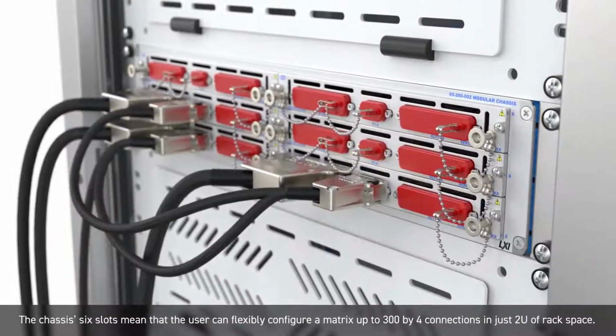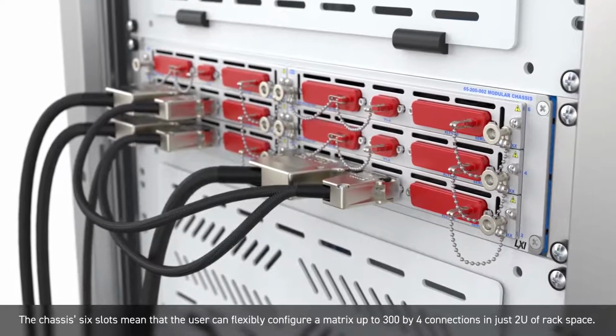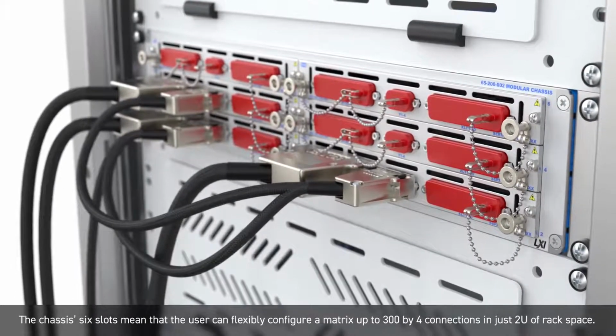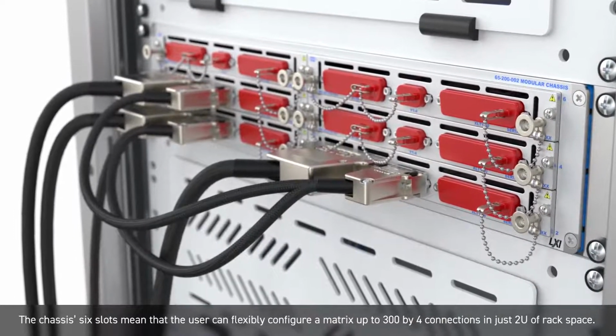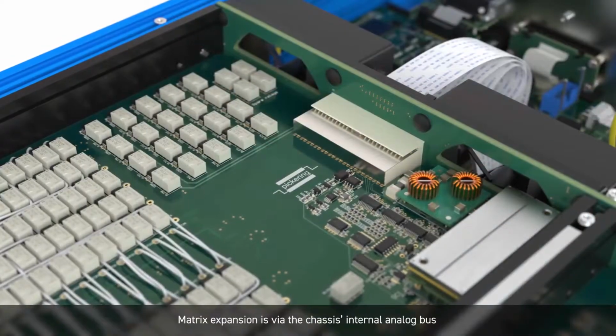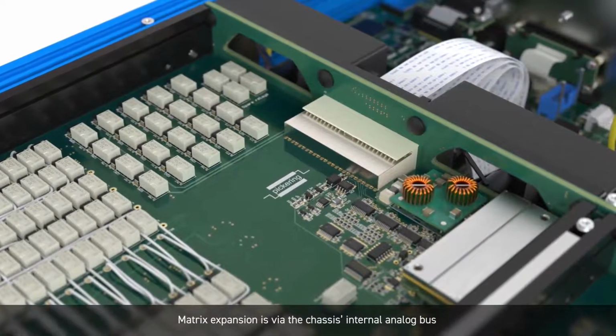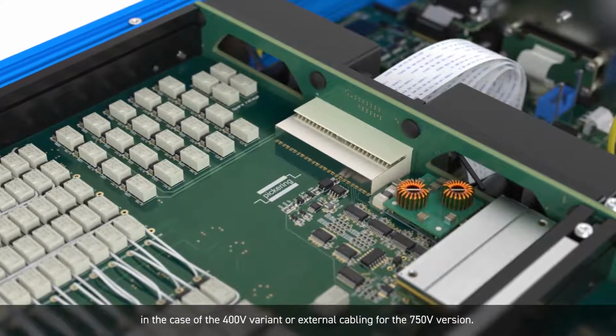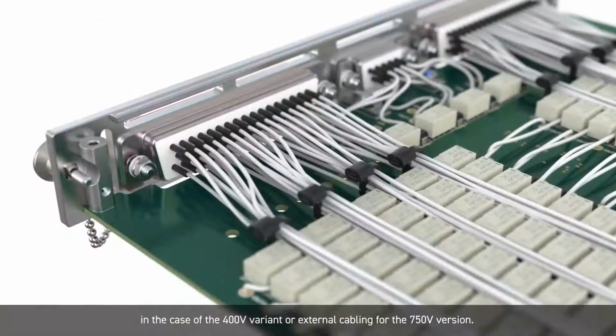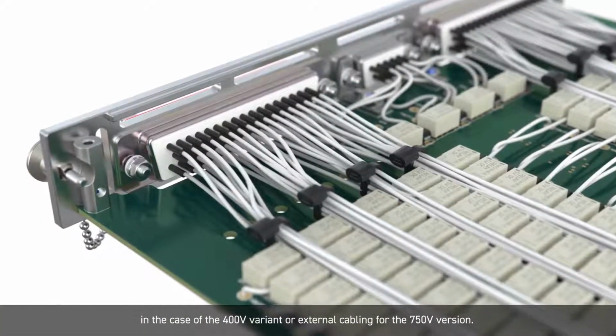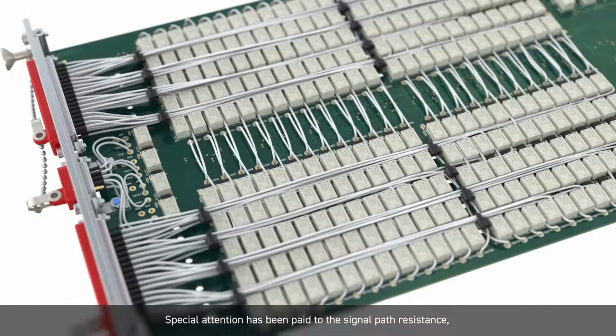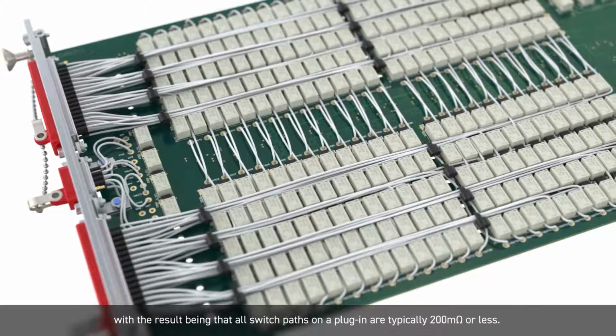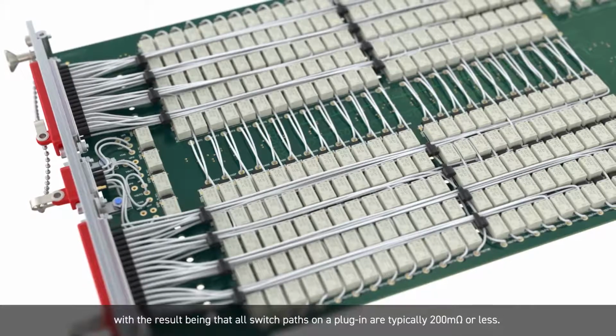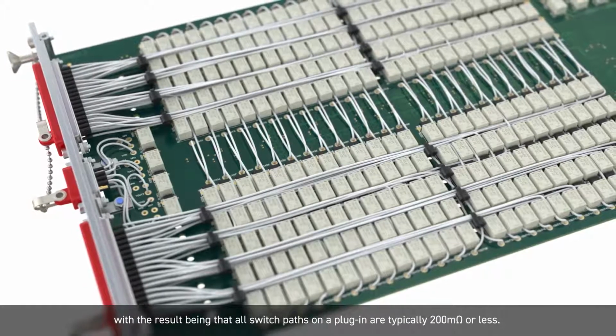The chassis' 6 slots mean that the user can flexibly configure a matrix up to 300x4 connections in just 2U of rack space. Matrix expansion is via the chassis internal analog bus in the case of the 400 volt variant, or external cabling for the 750 volt version. Special attention has been paid to the signal path resistance, with the result being that all switch paths on the plug-in are typically 200 milliohms or less.